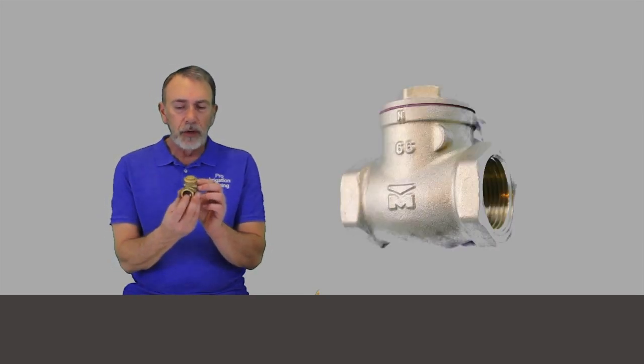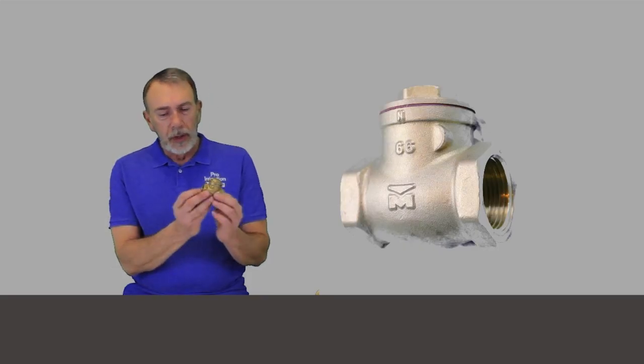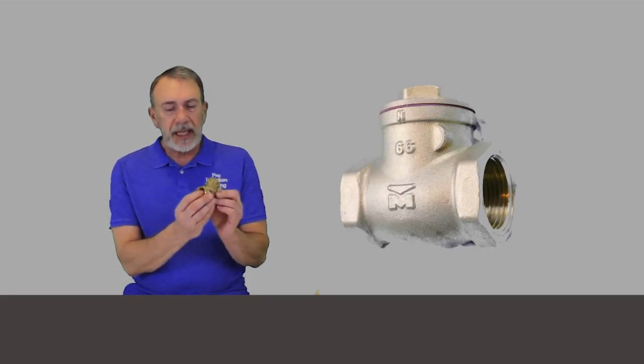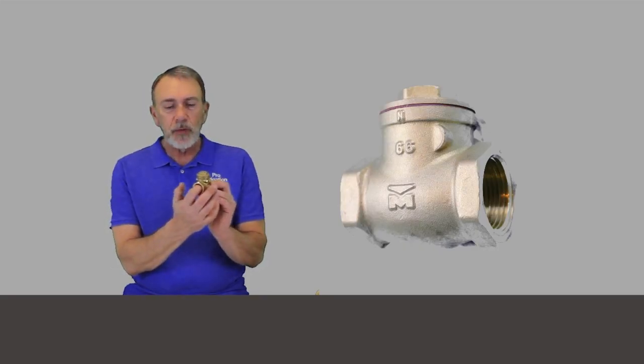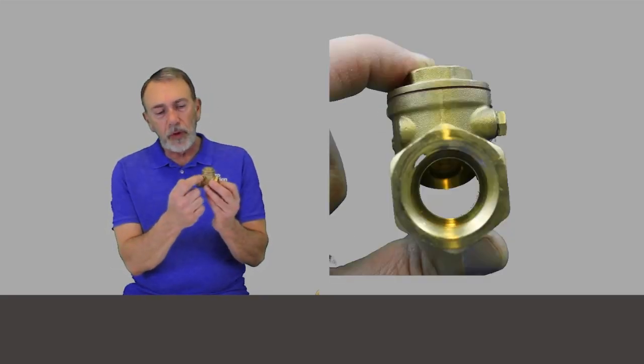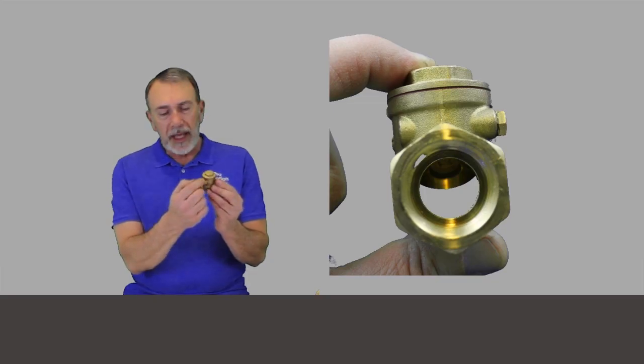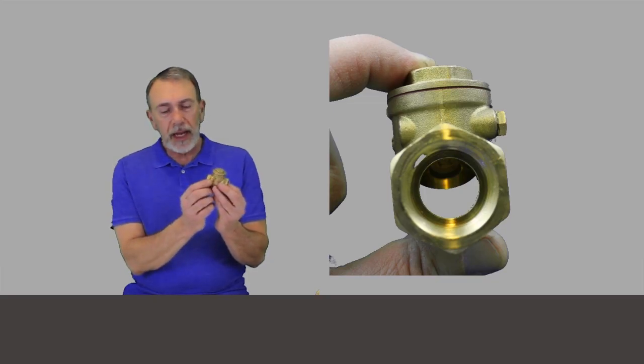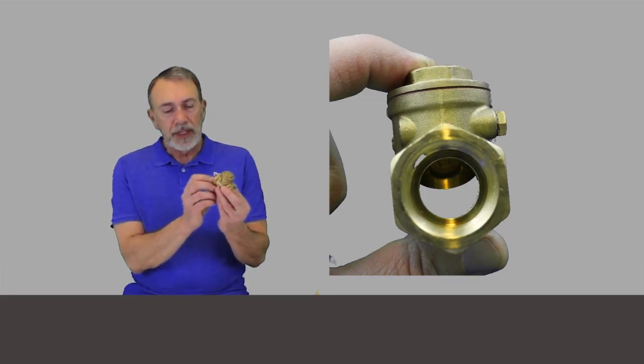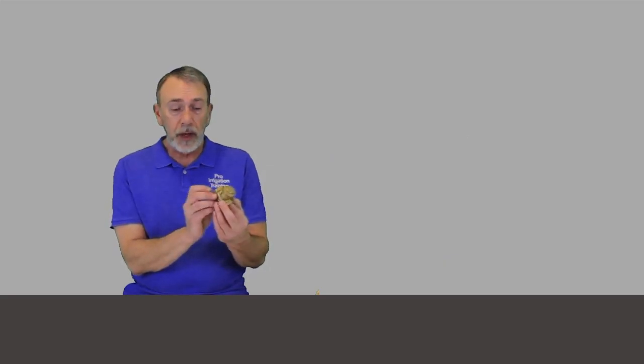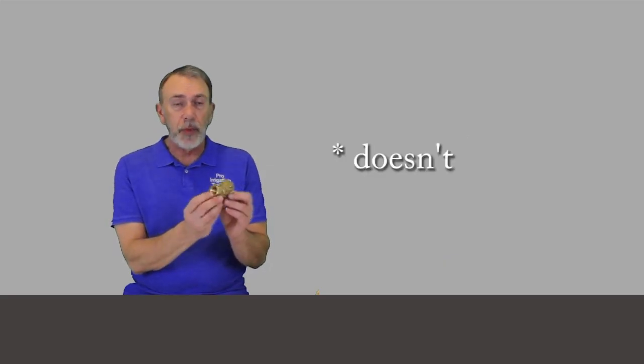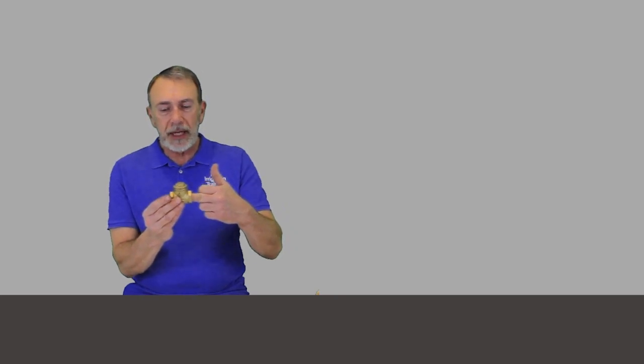Almost always a brass piece. All it's got is a little round disc in here that swings back and forth on a pivot, on a hinge here. And sometimes they have gaskets or an O-ring inside of them and sometimes they don't. This one don't. It's just brass on brass. The direction of flow is going this way and it swings that little thing out of the way. And water goes this way.